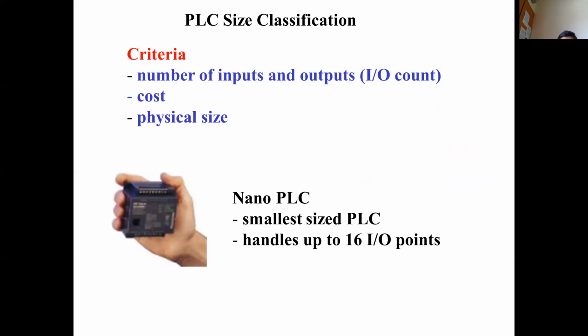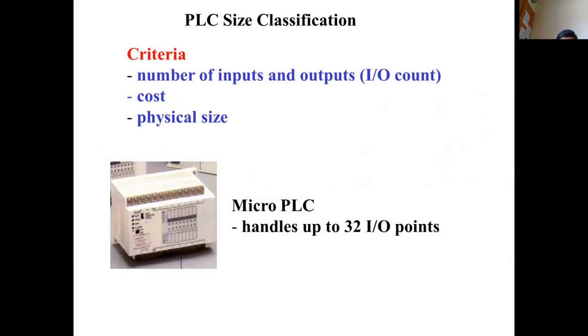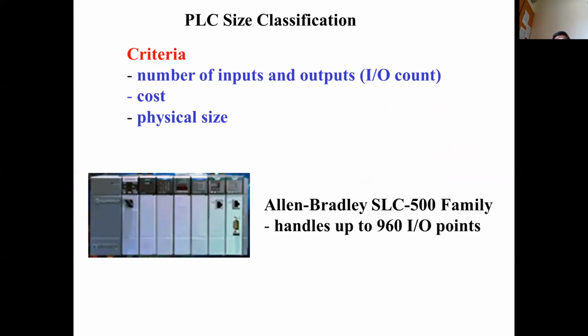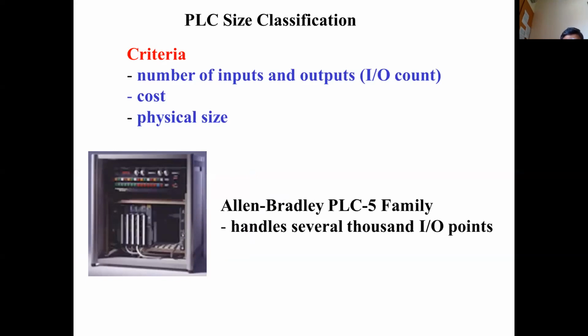So this is another type of PLC, a nano PLC. It can handle up to 16 inputs and outputs. And this PLC we have seen, that is a micro PLC. These come under the category of fixed PLC. Either a nano PLC or a micro PLC comes under the category of fixed PLC. And this one is a typical example of a modular PLC. First you have the power supply, then the processor, followed by the input and output modules. And this is a control panel where the PLC is built in.